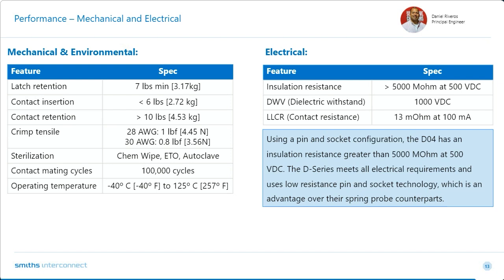Aside from being autoclavable, it can be chem wipe, ETO. So these 3 sterilization options are available. We are at about 100,000 cycles for mating, and the temperature is pretty standard, minus 40 C to 125 C. For electrical, we have insulation resistance of greater than 5,000 megaohms at 500 volts DC, our DWV, dielectric withstand voltage, is at 1,000 volts, and our LLCR, the contact resistance, is at 13 milliohms at 100 milliamps. One thing to note is that the D04 meets all the electrical requirements, and it uses low resistance pin and socket technology, which is an advantage over the spring probe counterparts.